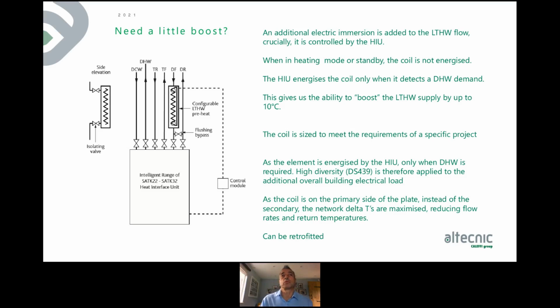Now, crucially, two things. One is that this is controlled by the HIU. It's only energized when you have a domestic hot water demand. So your additional electrical load in the building is diversified in the same way as you would do with DS439 for your domestic load anyway. So the additional load is really very, very small, additional electrical load. So that's the first aspect.